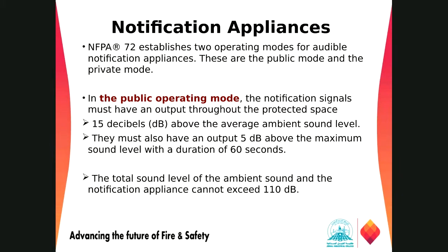The second one, they must also have an output 5 dB above the maximum sound level with a duration of 60 seconds. So whatever the maximum sound level in those areas lasting for 60 seconds, it should be higher than that.